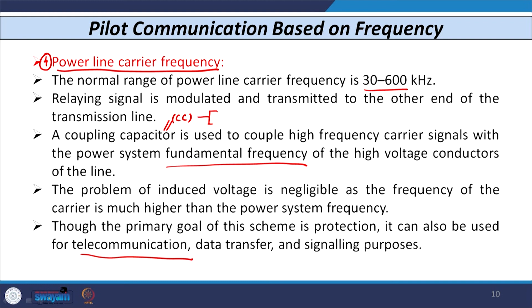Of course, if I use this scheme, we can use it along with teleprotection, and for other applications also, like telecommunication, data transfer, and signaling purposes. Communication purposes also can use such a scheme, known as power line carrier frequency. The next type of scheme, the fifth one, is based on radio frequency. In the earlier case, power line carrier frequency, we generate the high frequency carrier in the substation, superimpose it with the fundamental frequency and then transmit, whereas here in radio frequency the concept is entirely different.